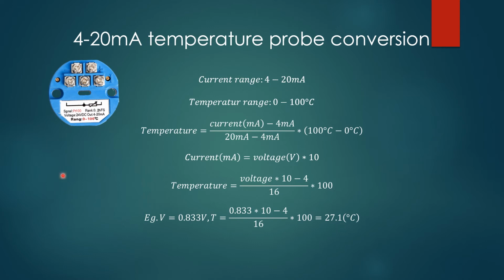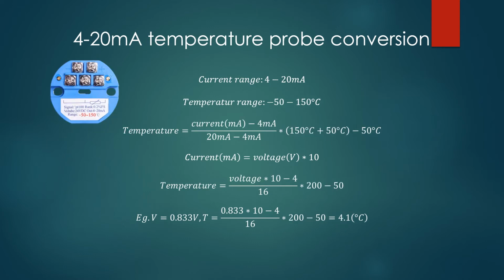So what if you have a different transducer? Here's another example: a different transducer that goes from minus 50 degrees C to plus 150 degrees C. It also requires the same signal from a PT100 and outputs 4 to 20 milliamps. So here we have a different temperature range to map, minus 50 to plus 150, from the 4 to 20. We do the same thing. We take the current readout, subtract the starting point, and then divide by the range. This gives us where we are in our temperature range.